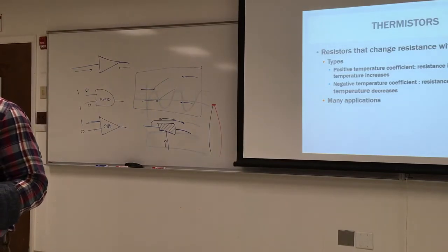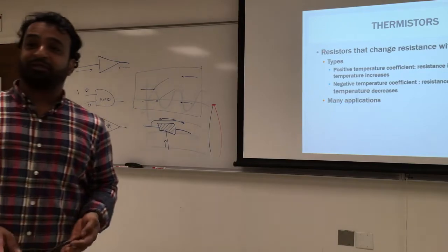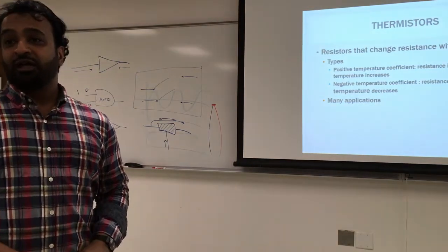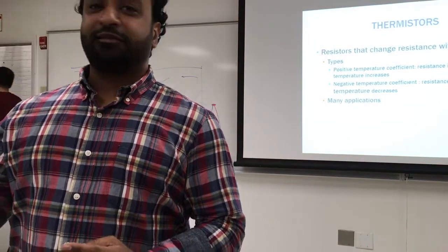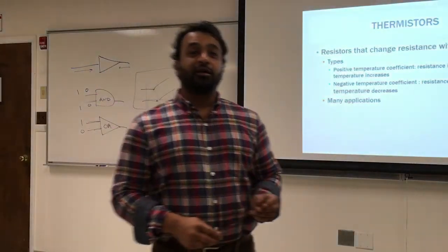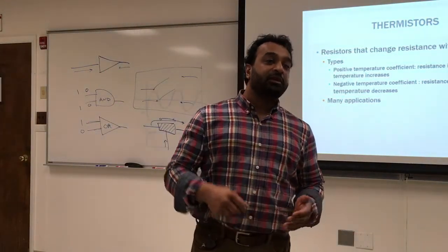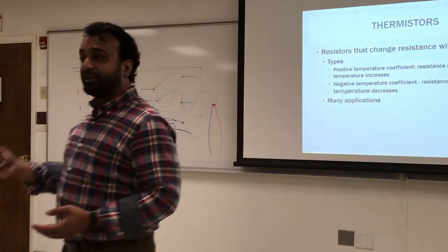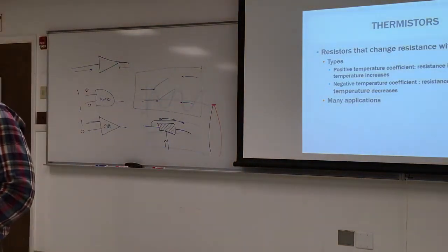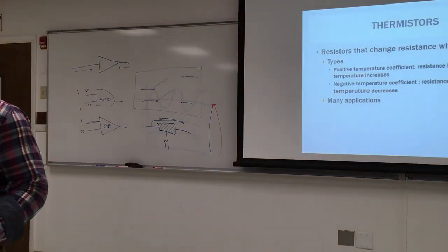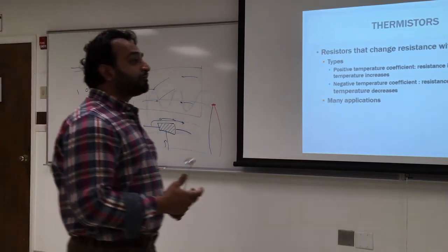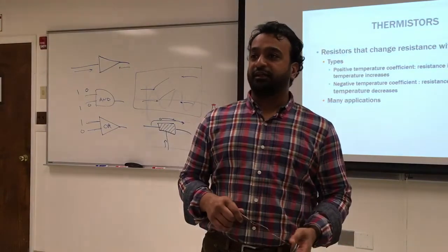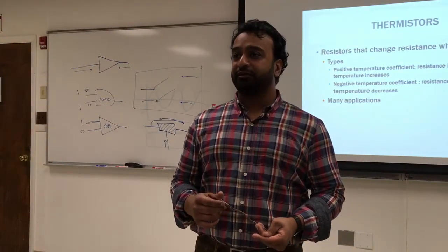Whenever you have any temperature controls or temperature sensors, check the limits and make sure you are within the limits. Otherwise, you might break it, or you might lose the calibration. If you go off the calibration, you change the properties of that sensor, and it's not going to function correctly anymore once you exceed it. Even thermostats have to be calibrated every once in a while.